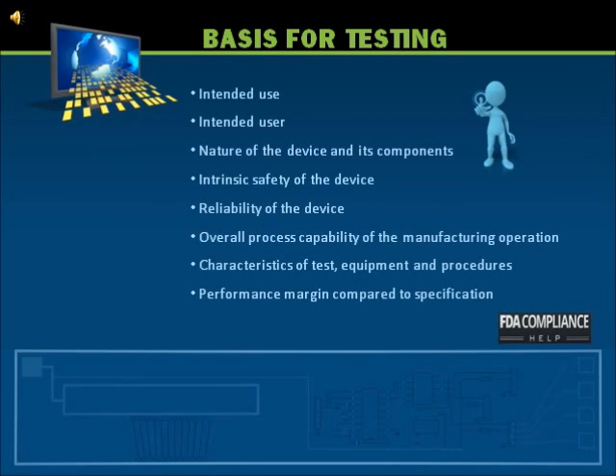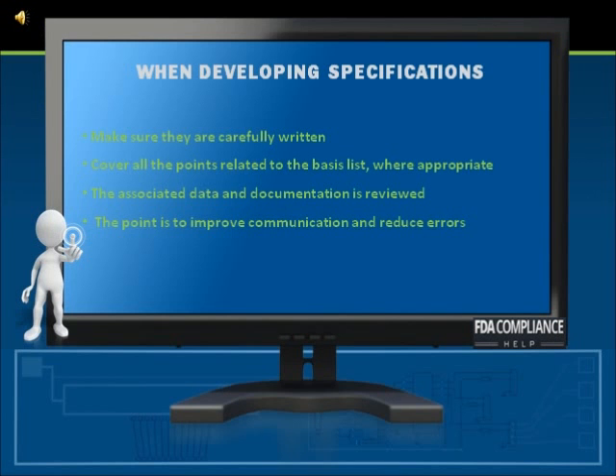These decisions are typically based on intended use, intended user, nature of the device and its components, intrinsic safety of the device, device reliability, overall process capability of the manufacturing operation, characteristics of test and inspection equipment and procedures, and performance margin of the device compared to the device specification. Device test and inspection specifications, as well as test and inspection procedures, should be carefully written and shall cover all appropriate points in order to improve communication and reduce errors.